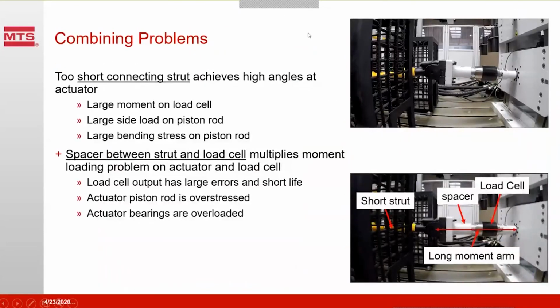This is kind of an interesting one. The problem here is we have a short connecting strut to a multi-axial loading situation. That short connecting strut puts a high angle here on this load cell, and with a spacer on the end of the load cell besides, that really increases the prying moment. And you can see here, physically, what it's doing to the load transducer. Large moment on load cell, large side load on piston rod, large bending stresses on piston rod. I predict this actuator has a short life.